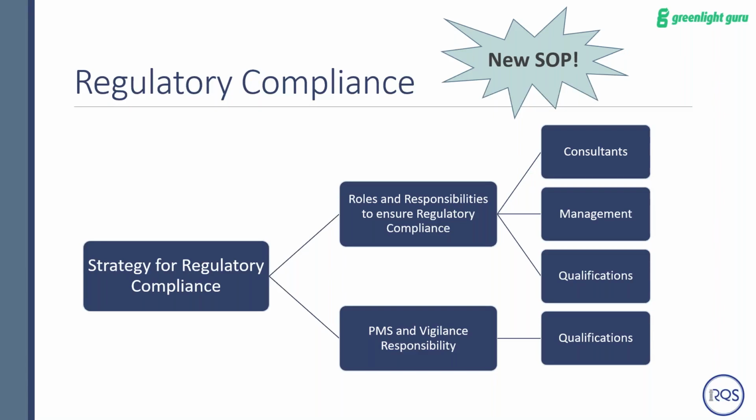Some additional details on this role. It's responsible for post-market surveillance obligations, that reporting obligations are fulfilled, that the technical documentation and declaration of conformity are kept up to date, and that the device is appropriately controlled within the quality system. So that's general quality system stuff, but additional, more detailed things that should be defined in that job description as well.